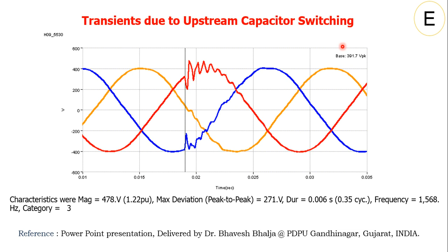Similarly, transients have some causes and effects. Some possible causes are power factor capacitor energization, lightning surges. It might be due to loose connection or chattering. There might be load or source switching. For example, if a 20 kilowatt induction motor is connected with the grid, then nothing happens to the grid. But if such 20 kilowatt induction motors across a particular industrial sector are connected with the grid, there might be a transient, what we call a switching transient, that could be caused. And such renewable energy sources should be able to withstand this transient without tripping themselves.